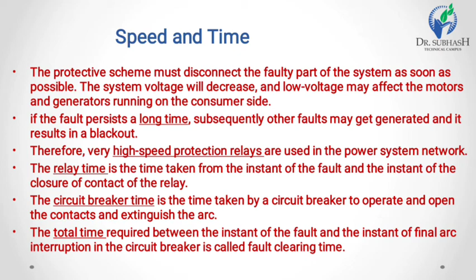The relay time is the time taken from the instant of fault to the instant of the closure of the contact of the relay. The circuit breaker time is the time taken by the circuit breaker to operate, open the contacts and extinguish the arc. So the total time between the instant of fault and arc interruption is the total fault clearing time. So a desirable quality of protective relaying is high speed operation of relays.